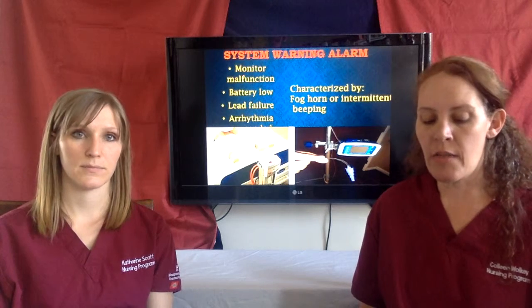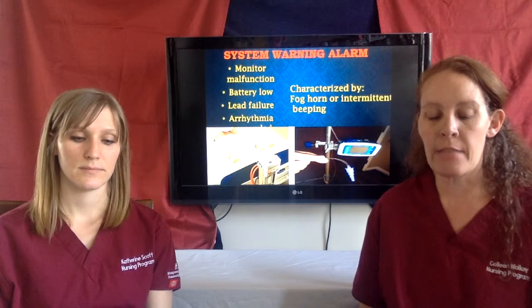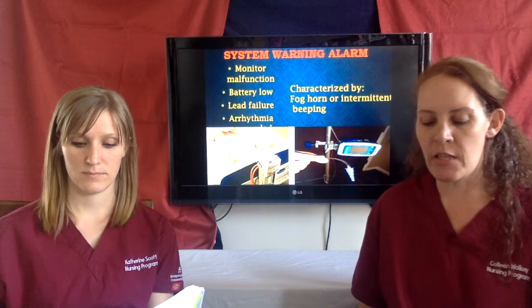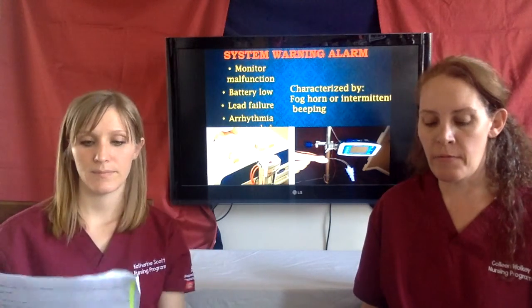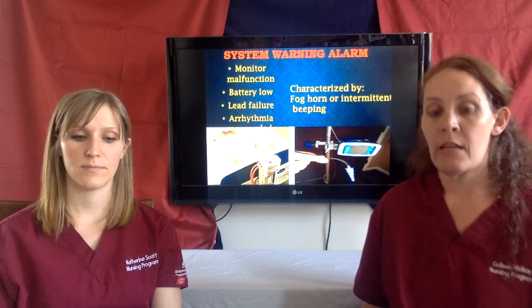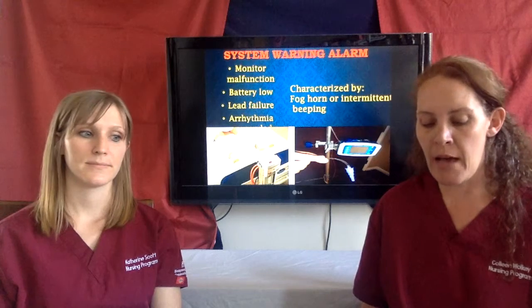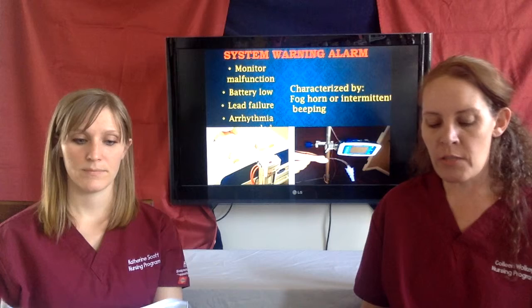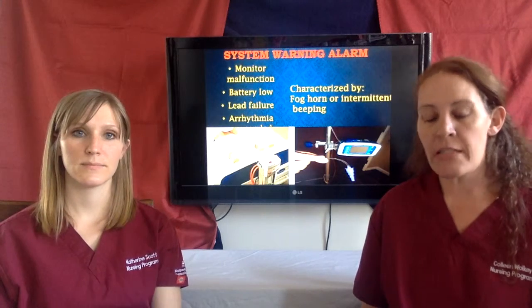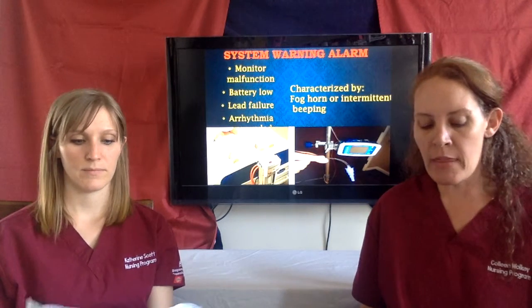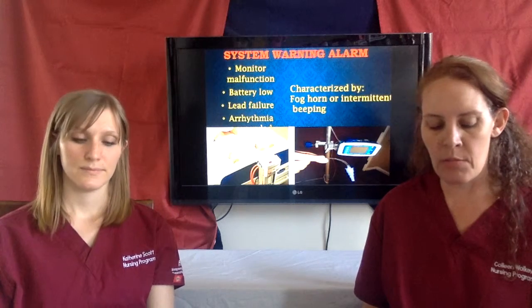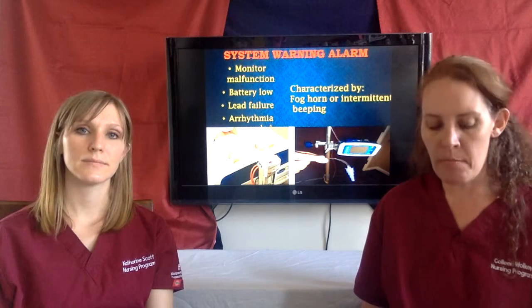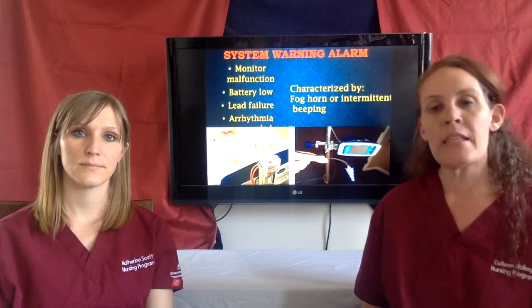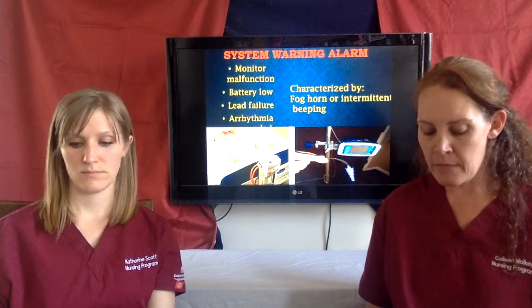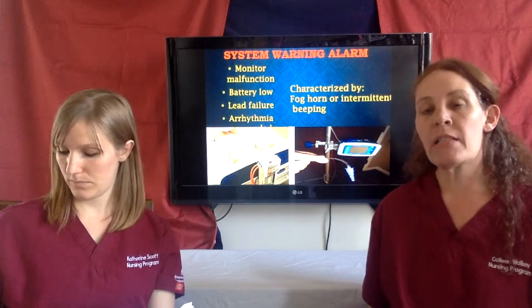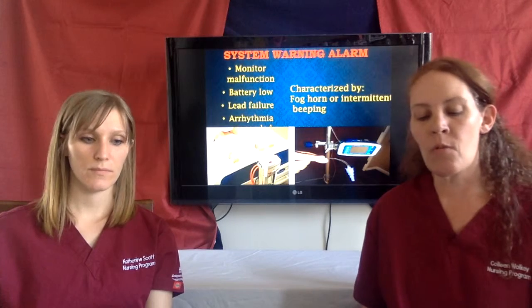In a research study conducted in 2007, a medical progressive care unit was selected as a pilot unit for a quality-based improvement initiative that would enable the task force to quantify the frequency of cardiac monitor alarms on a single unit and to perform small tests of change to improve management of these monitor alarms. The task force was instructed to collect data from the cardiac monitors based on the alarm levels for 18 days. And what they found was that 90% of the cardiac monitor alarms were simply advisory alarms. Alarms on medical devices are designed to let healthcare professionals know that some kind of attention is required, either for the device or for the patient. Alarms are essential because an important nursing intervention may be required in order to avoid an adverse event.